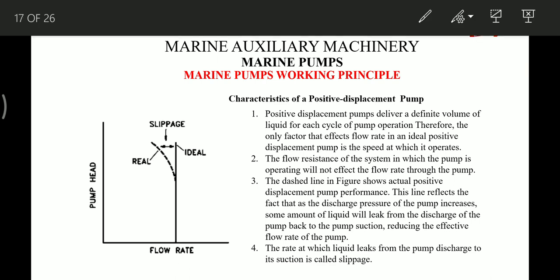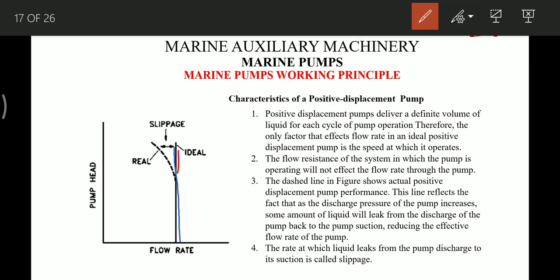The characteristic curve for the positive displacement pump shows no change in flow rate with increasing pressure — it is ideally a straight vertical line. In a real situation, however, there is slippage, so the actual characteristic curve has a slight lean — the actual curve looks slightly different from the ideal.